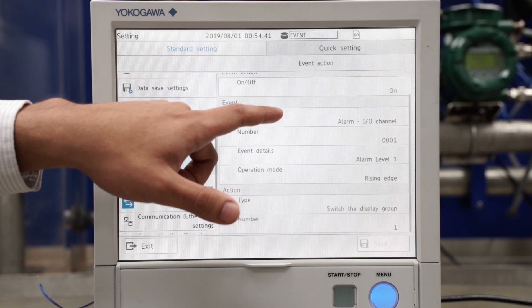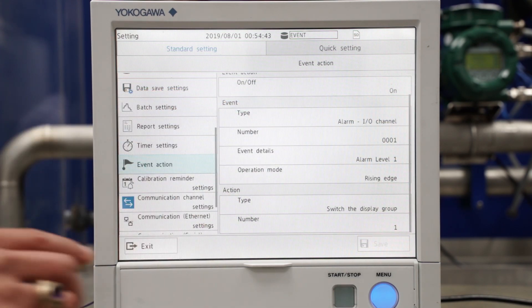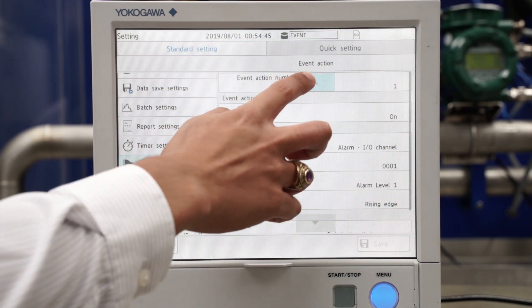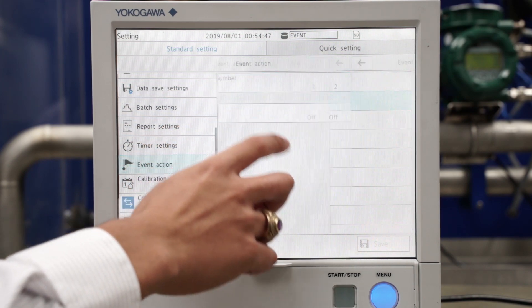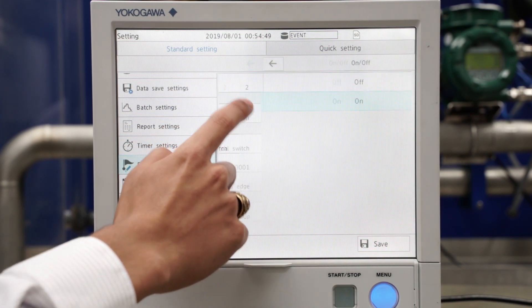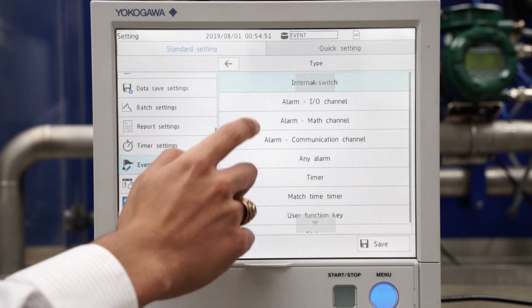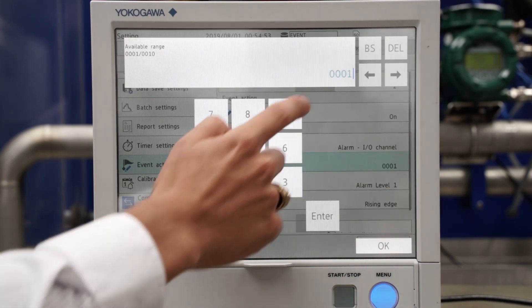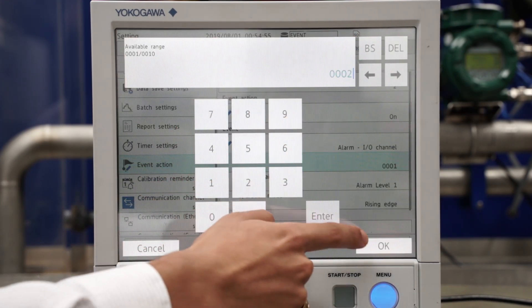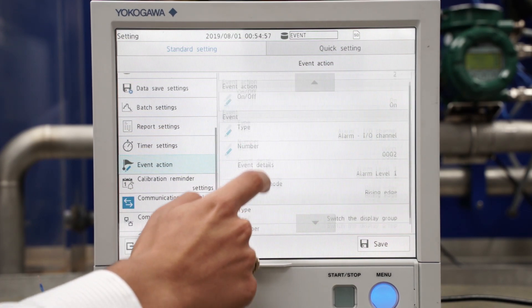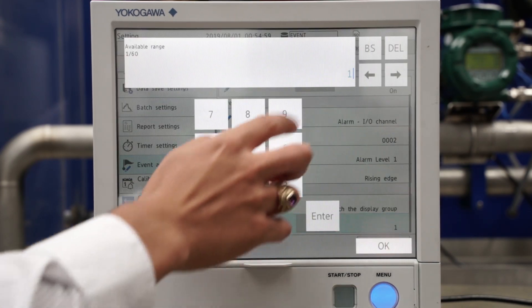And I'll go to event action number two. I'll turn that one on, I'll make it an alarm as well but for channel two, and I'll have the action be switch the display group to display group two. I'll save that.